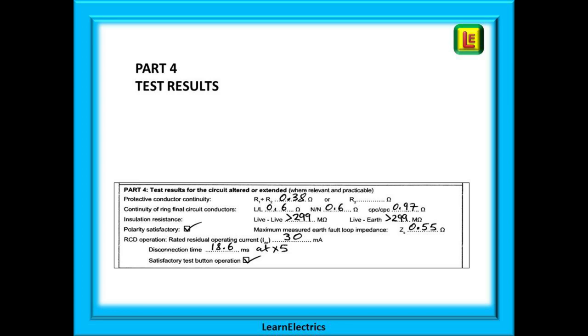In Part four we will enter our test data. You should already know how to test for all these parameters, but LearnElectrics has produced some videos if you need a quick reminder. R1 plus R2 is recorded, or just R2 if you are replacing or upgrading the earth or bonding conductors. Insulation resistance will need to be measured and recorded, as will loop impedance, polarity checks, and RCD tests.